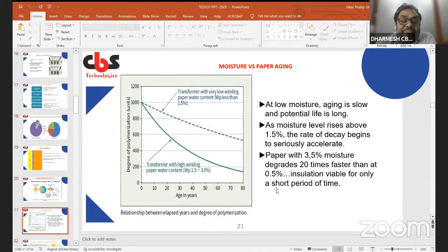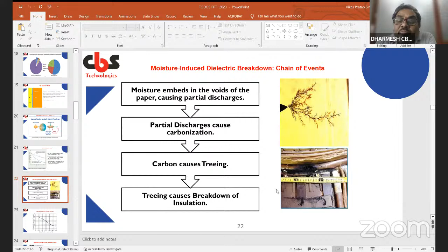Next, this is how the paper looks in practice as it degrades. Moisture embedded in the voids of the paper causes partial discharges, partial discharges cause carbonization, carbon causes treeing as you can see in the first slide, and the tree causes breakdown of the insulation. You can see below how the paper gets deteriorated.